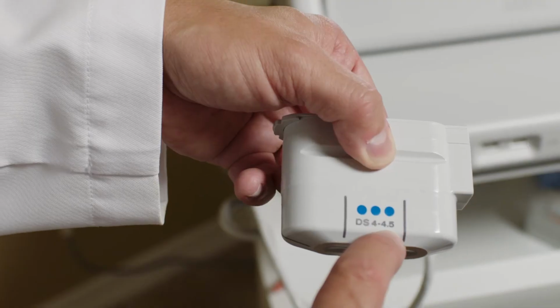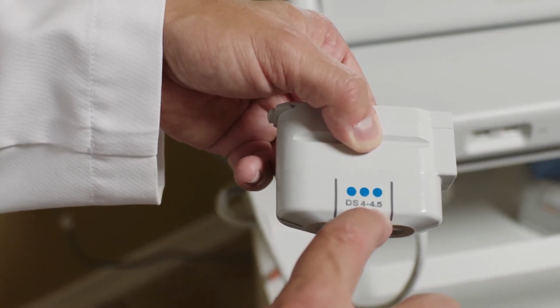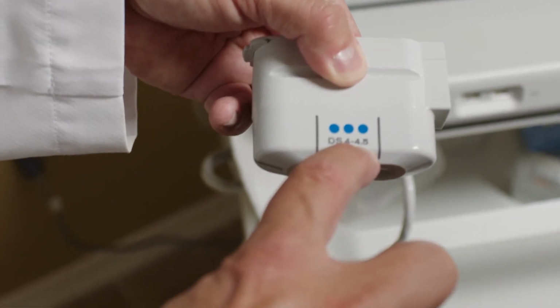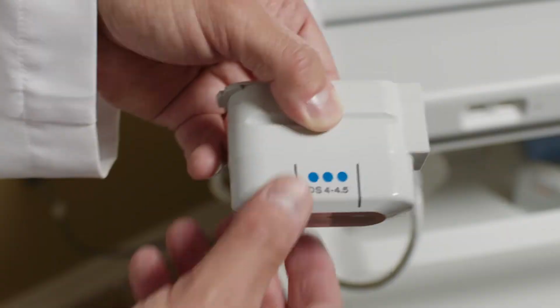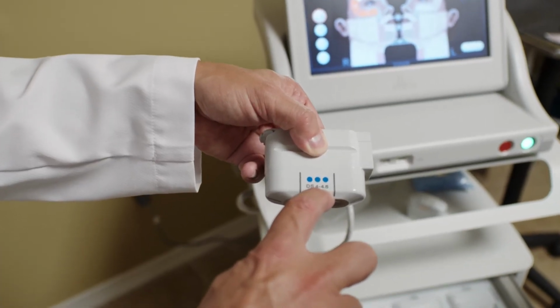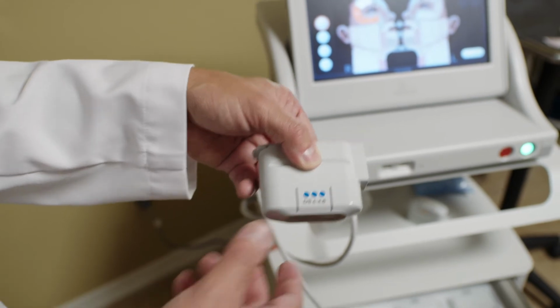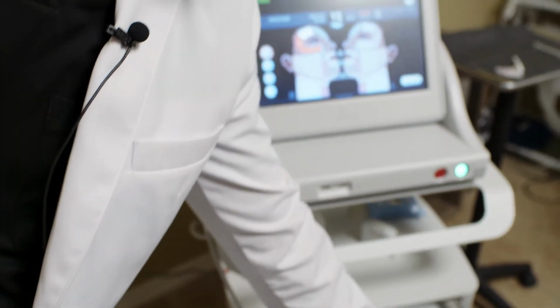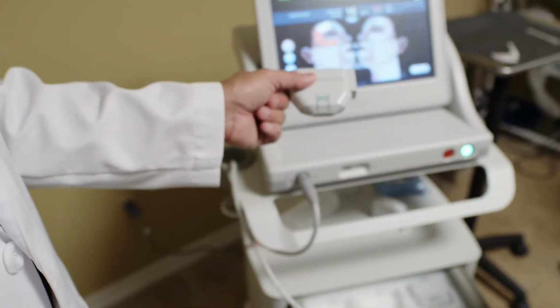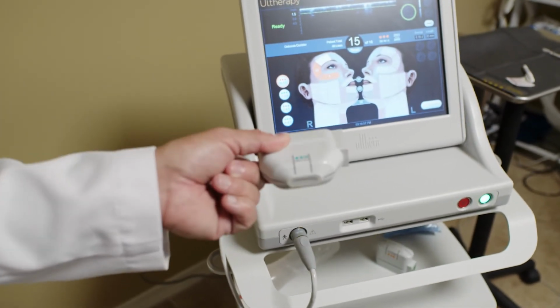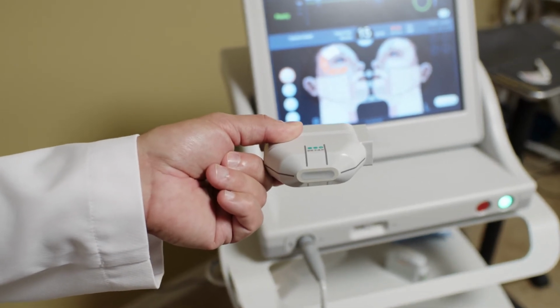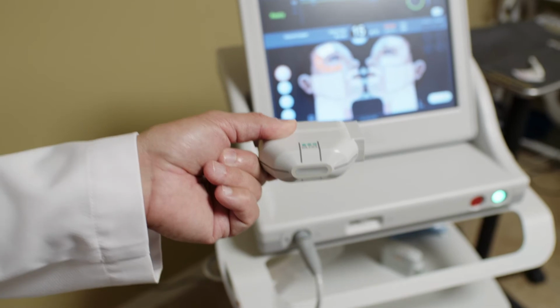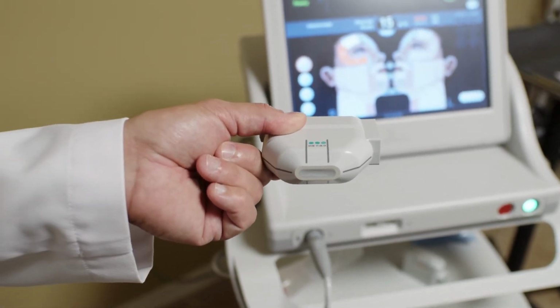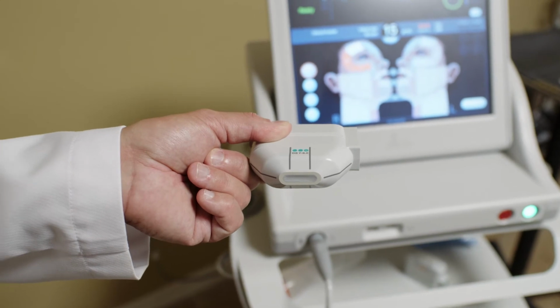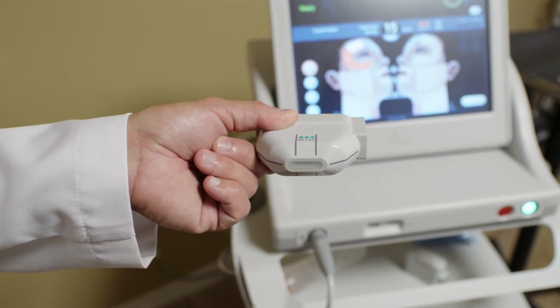Now we have different heads in here, so this is a 3 millimeter head, but as you look, we also have, this is a 4.5 millimeter, and the size of the head controls the depth as to where we're delivering our energy. And the way that we're going to determine the appropriate depth is scanning the patient. So we will scan them with real-time ultrasound, view our ultrasound imaging, and then we will use our device to deliver the energy. Now this is a 3 millimeter head. This is a narrow head, and so this is one that we can use for treatment of perioral lines, either above or below the lip. Also, we can use this for some areas occasionally if we need to deliver a narrow band of energy when we're working around the brows.